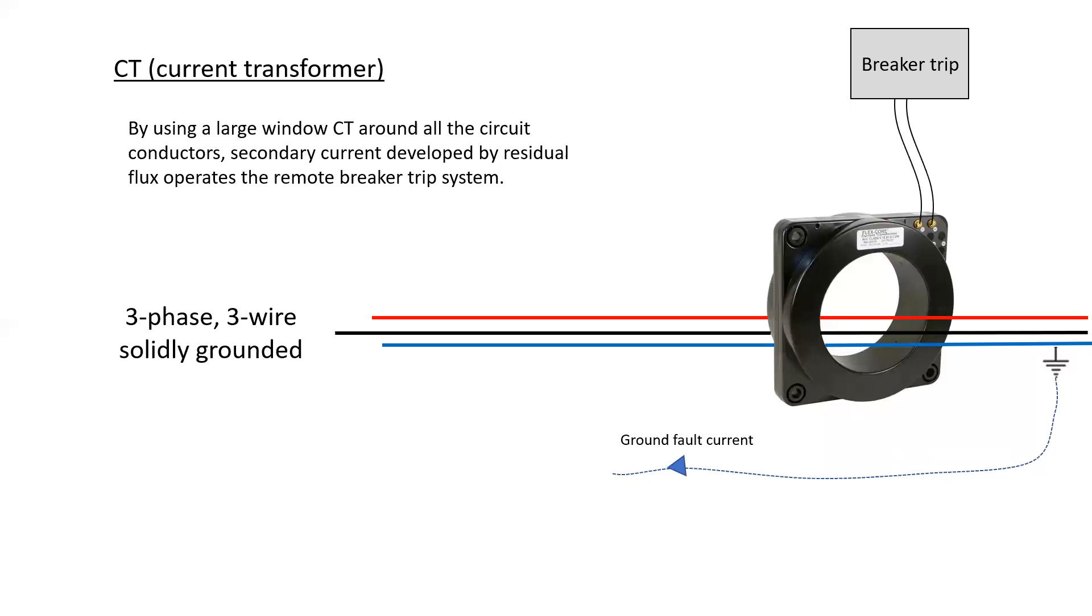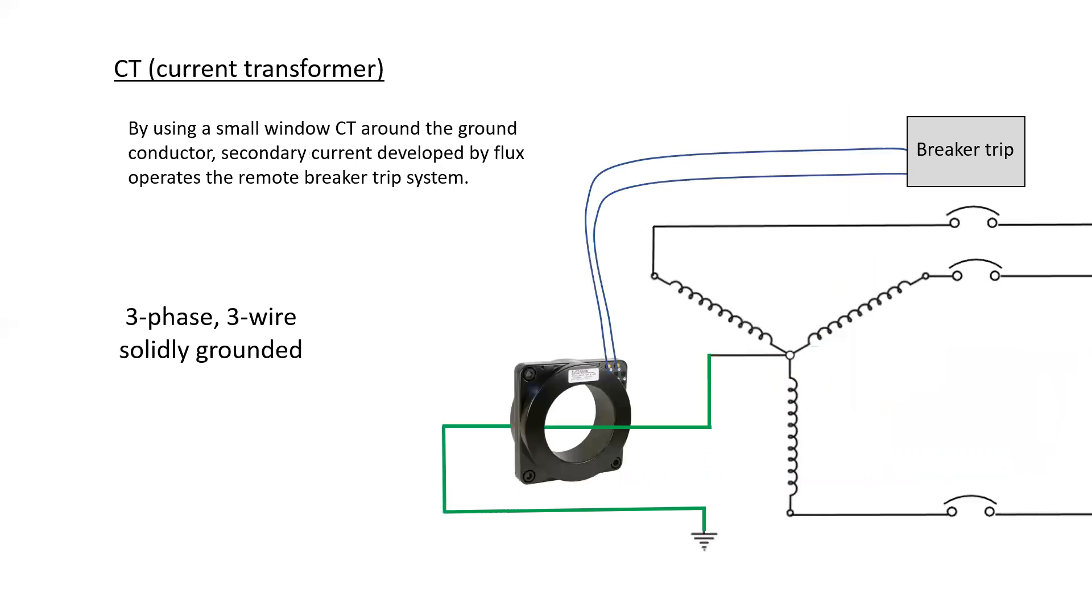If we use a large window CT around all the circuit conductors, secondary current developed by the residual flux will operate the remote breaker trip system, often referred to as a shunt trip. Alternatively, we could use a small window CT around the ground conductor and the secondary current developed by the flux, when there's current flowing through that ground conductor will operate the remote breaker trip system.